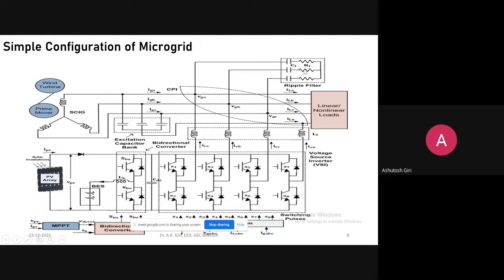Why is high pass filter used? Why is current ripple filter used? Basically, ripple filter is needed to shape up the current coming from the pulse width modulation technique, and high pass filter is needed to provide one path for the high frequency components created from the switching operation of this inverter unit. If we don't provide this kind of arrangement, they may propagate towards the generator or towards the load. Either way, they will create problems, so we have to provide an alternative path. That's why it is known as high pass - high frequency components will be circulated in this.